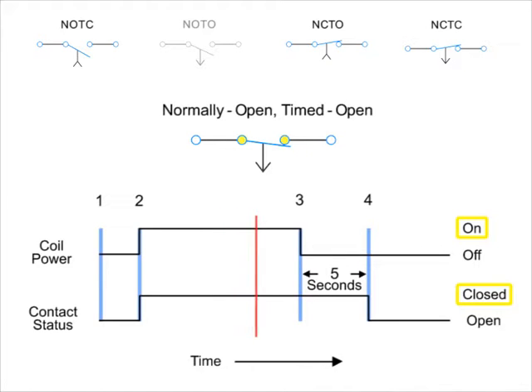However, unlike the NOTC contact, the timing action occurs after the coil is de-energized for five seconds. Thus, the contacts close immediately when the coil is energized and open five seconds after the coil is de-energized.